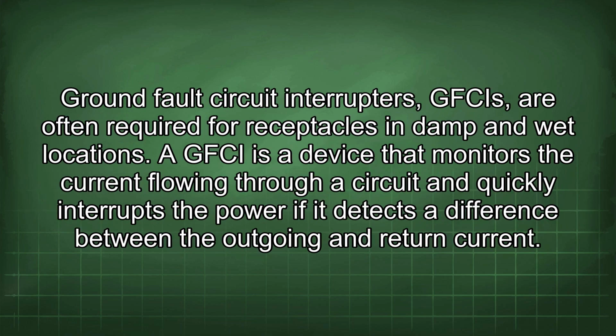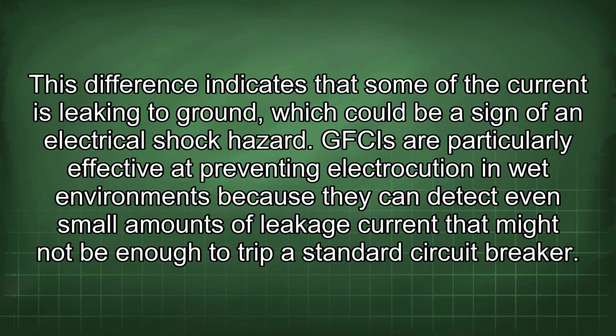Ground fault circuit interrupters, GFCIs, are often required for receptacles in damp and wet locations. A GFCI is a device that monitors the current flowing through a circuit and quickly interrupts the power if it detects a difference between the outgoing and return current. This difference indicates that some of the current is leaking to ground, which could be a sign of an electrical shock hazard. GFCIs are particularly effective at preventing electrocution in wet environments because they can detect even small amounts of leakage current that might not be enough to trip a standard circuit breaker.